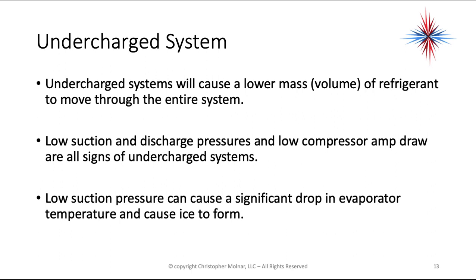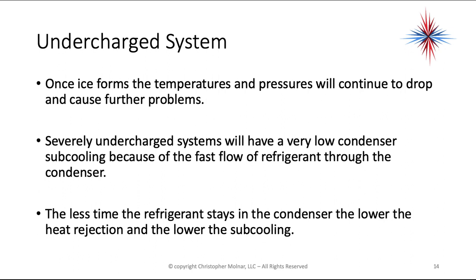Undercharged systems are also important. We have to make sure we're not looking at a kinked line because some of the characteristics are similar. Undercharged systems will cause a lower mass — that's a volume of refrigerant — to move through the entire system. Low suction and discharge pressures and low compressor amp draws are all signs of an undercharged system. Low suction pressure can cause a significant drop in evaporator temperature and can cause ice to form. Once ice forms, temperatures and pressures will continue to drop and cause further problems. Severely undercharged systems will have very low condenser sub-cooling because of the fast flow of refrigerant through the condenser — the less time refrigerant stays in the condenser, the lower the heat rejection and the lower the sub-cooling.